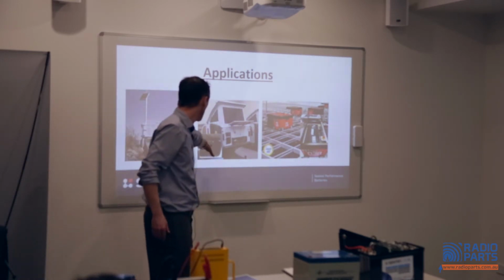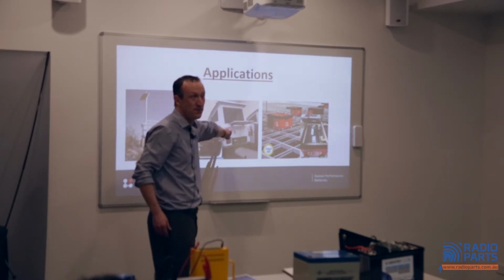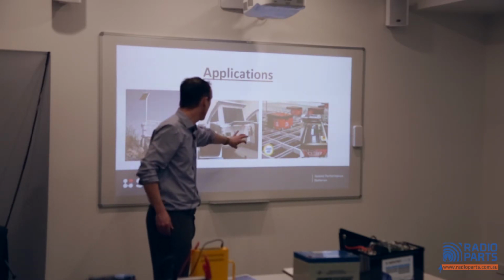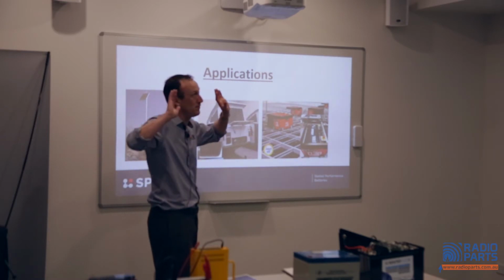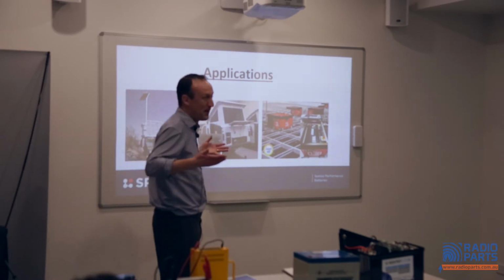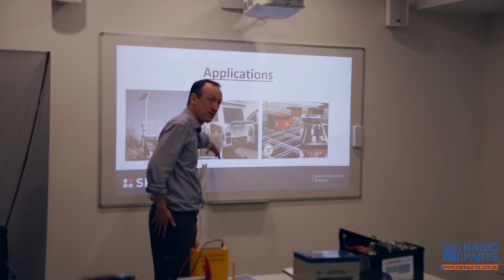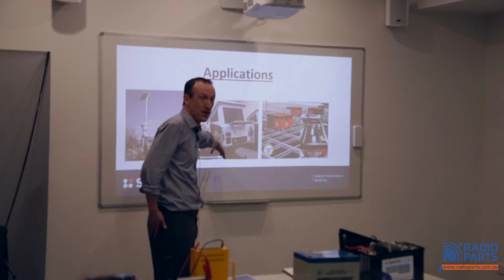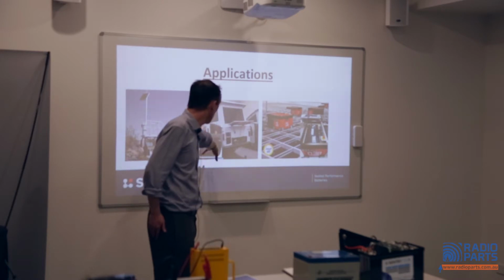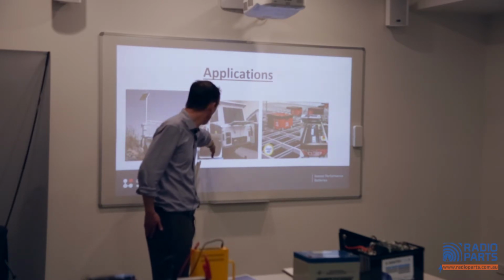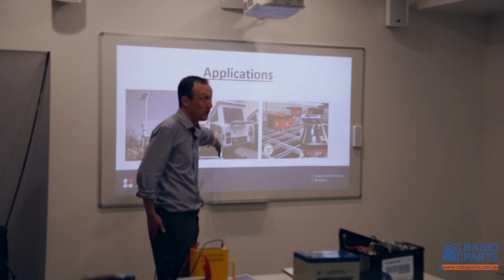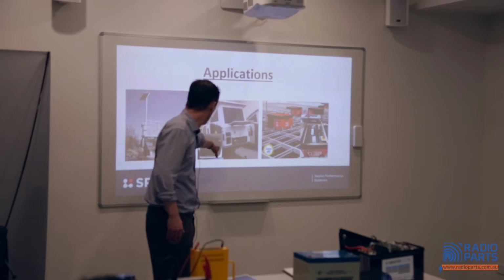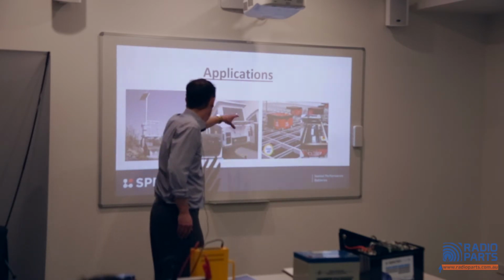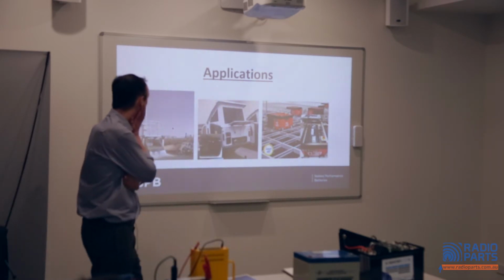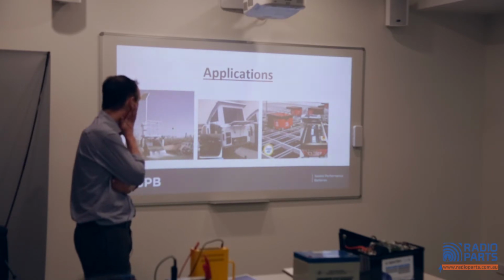The obvious application I spoke about before - this is another one of my customers, Vista RV Crossover in Bayswater. They've got off-road campers that can do the Canning Stock Route and ride on the moon. In this instance they wanted to use two lithiums in parallel, maintaining the same voltage as before. So they've got two 125 ampere hour lithiums wired in parallel to give 250 ampere hour, which is more like 300 or 350 ampere hour compared with lead acid. They've put them in the back of the unit here - a very common cyclic application.